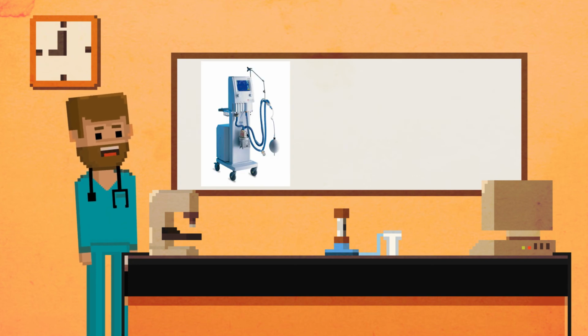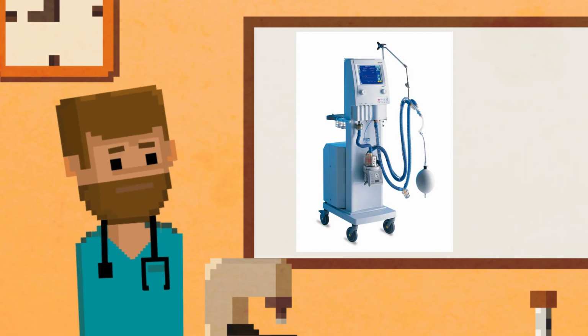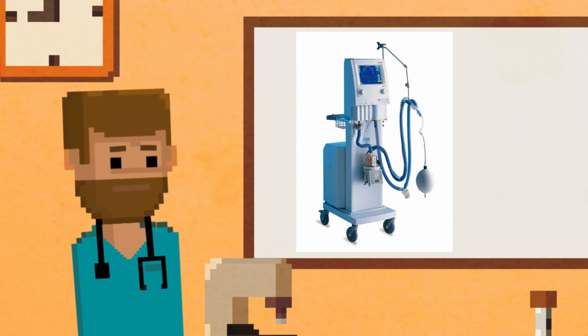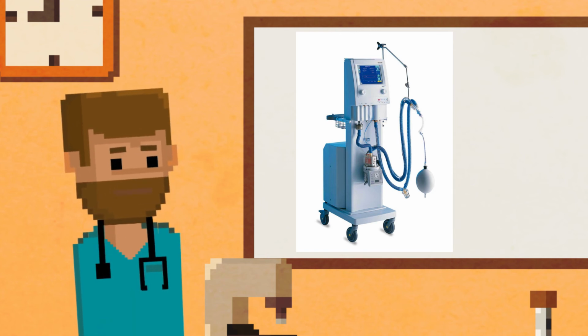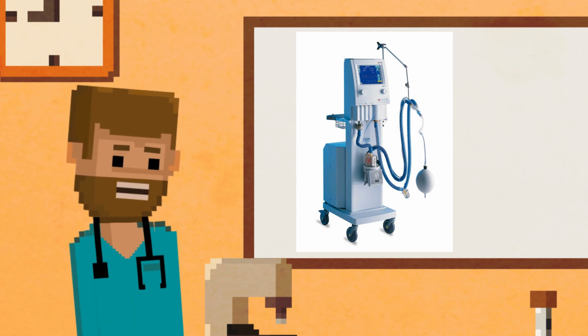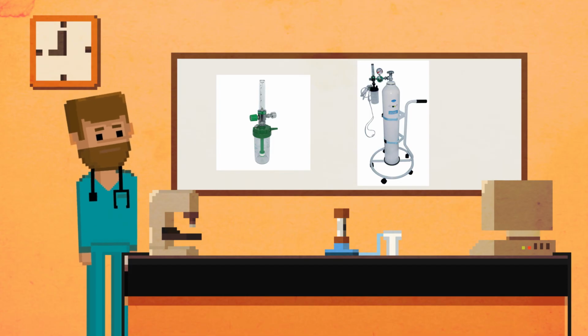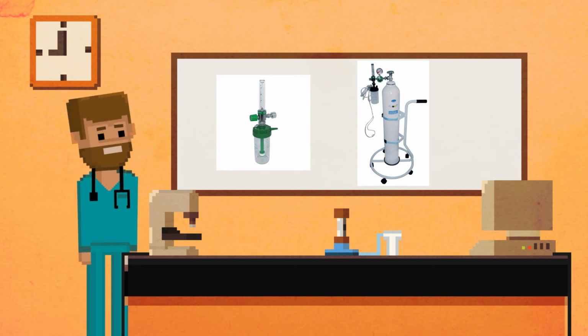So ventilators can also cause infection. The internal workings of ventilators are not common sources of infection, but the external ventilator circuitry poses the most significant contamination risk, particularly in systems using heated humidifiers. The primary problem stems from contaminated condensate in the inspiratory limb of the circuit. Oxygen therapy apparatus don't usually cause as many problems except for the non-disposable types. So many hospitals use disposable, and they can last up to 6 to 12 days.